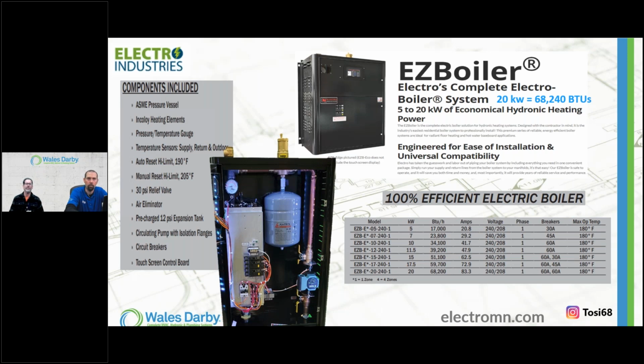Really? For that size home that you told me you had? Are you heating the neighbor and the neighbor behind them? Because in theory, unless we do a heat loss, in an existing home, chances are the electrical panel will not handle this new piece of equipment, all electric, for 140,000 BTUs worth. Let's turn around, do an example, do a heat loss. Well, you only need 60,000 BTUs, not 140,000. Now let's go back to the panel. Can we support double breakers, maybe two 60 amp breakers, or a 60 and a 45 amp breaker? So there is a little bit of knowing, walking through the demand. Well, can the house carry it?